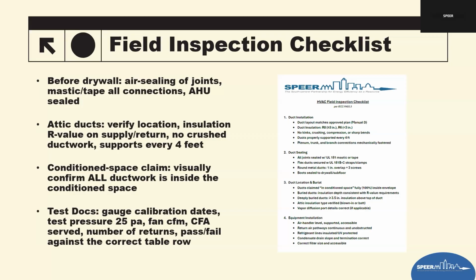Then look at the test pressure, that it's actually 25 pascals, because that's the requirement. Then the measured fan airflow, basically in CFM. So what was the CFM? But that doesn't tell you whether it passed or failed. What you really want to see is the CFM per 100 square feet, not just the CFM that was tested. A lot of forms that I see from the city still just say CFM. Then the city building official will have to do the calculation to find out, does it actually meet that target?